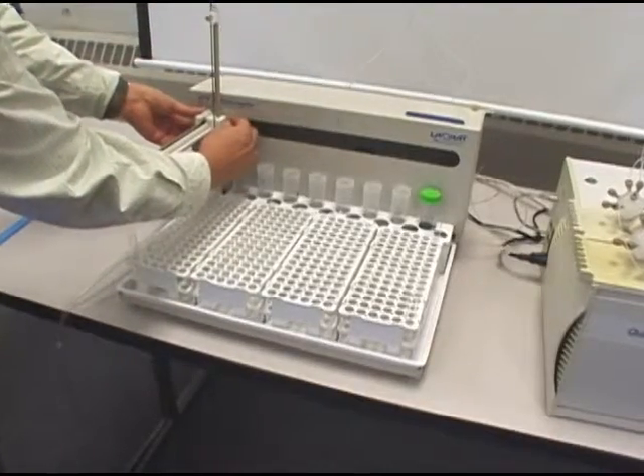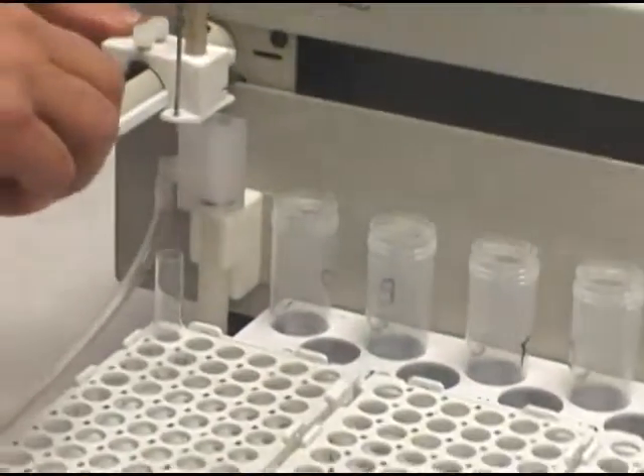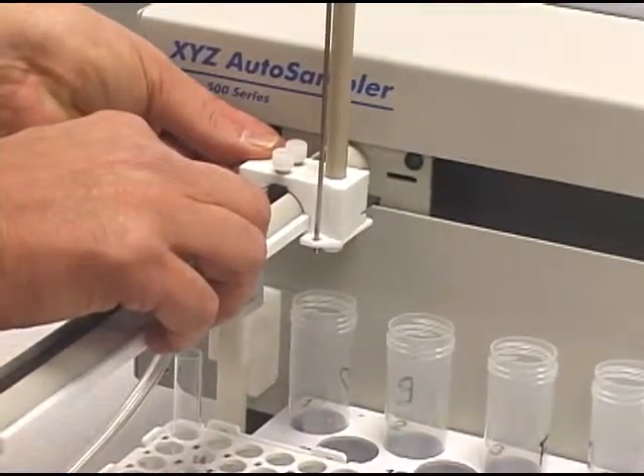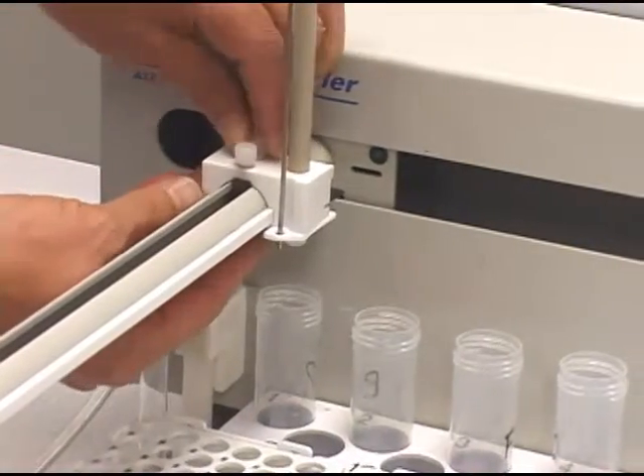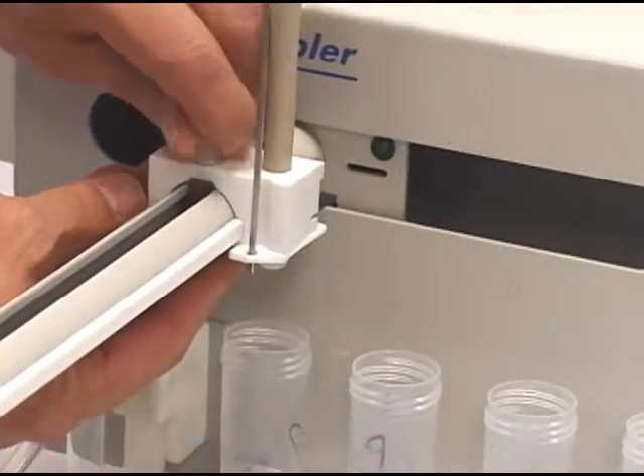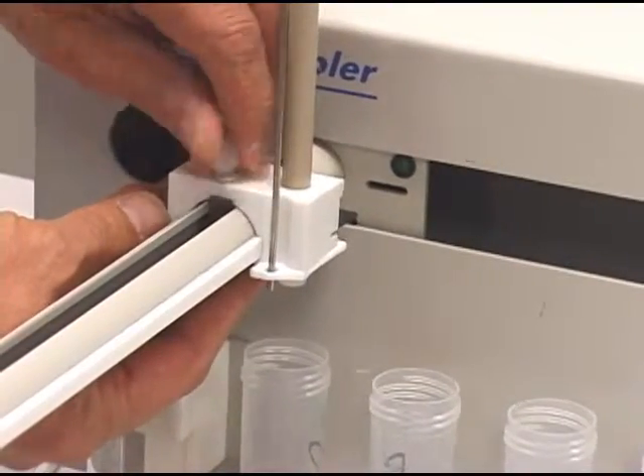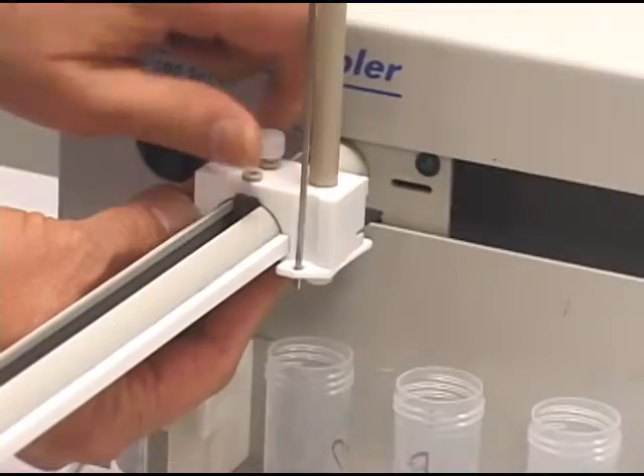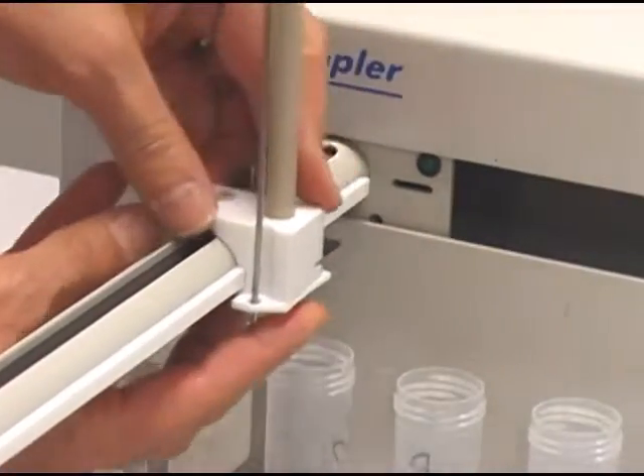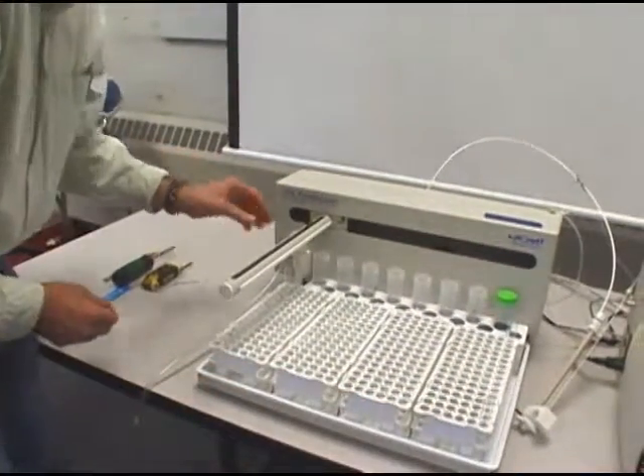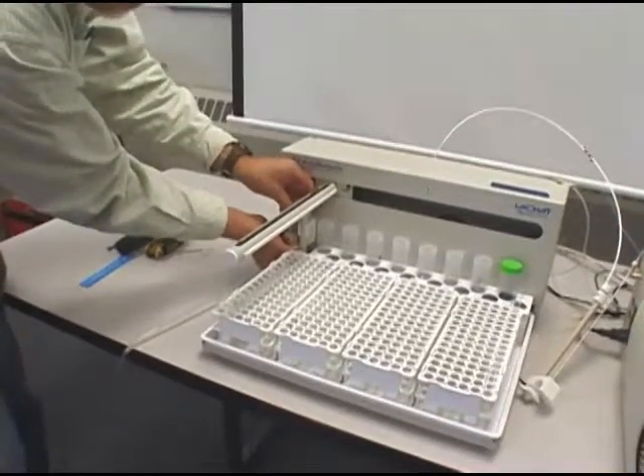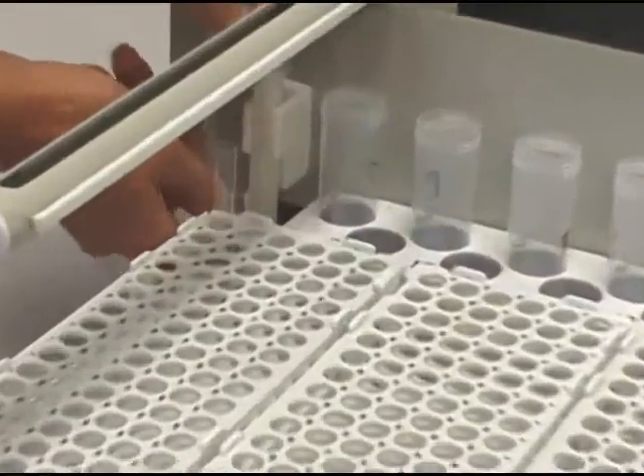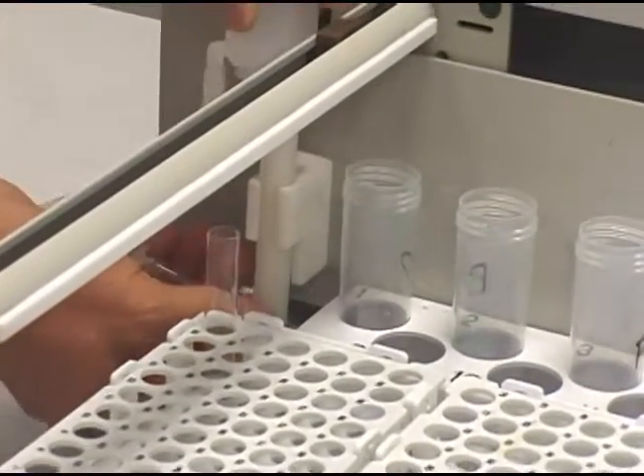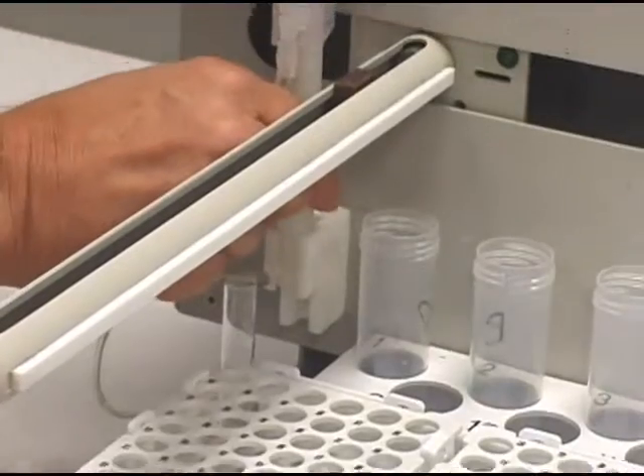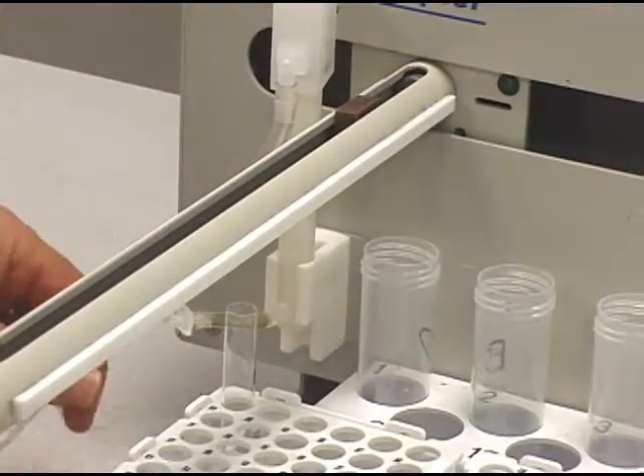I can pull then the mount forward a little bit, and then also slide it a little bit out of the way. We'll then go ahead and move the probe assembly by removing these 2 nylon screws. Set them to the side. Slide the assembly off. Set it to the side. And now I want to pull the wash bath out of position. Slide that up. And actually, you don't have to pull it all the way out. You can leave it somewhat in.